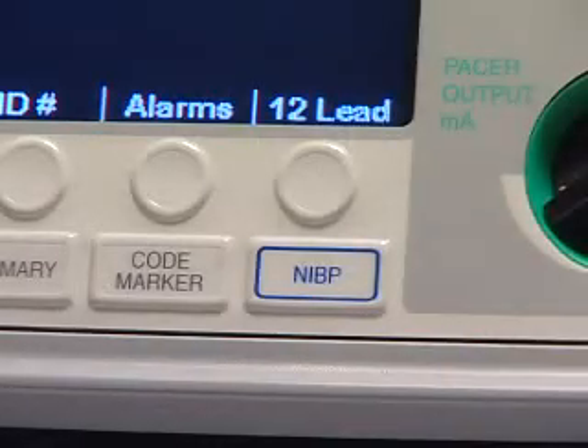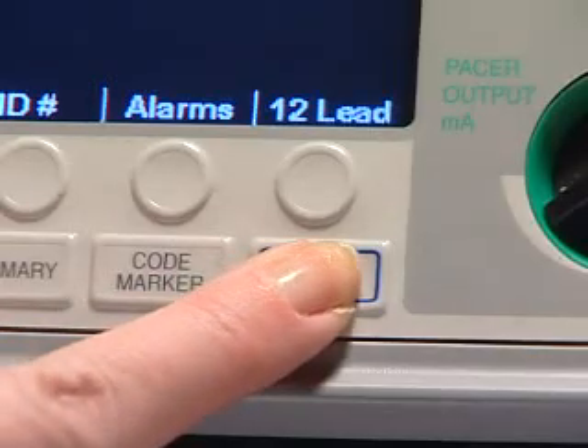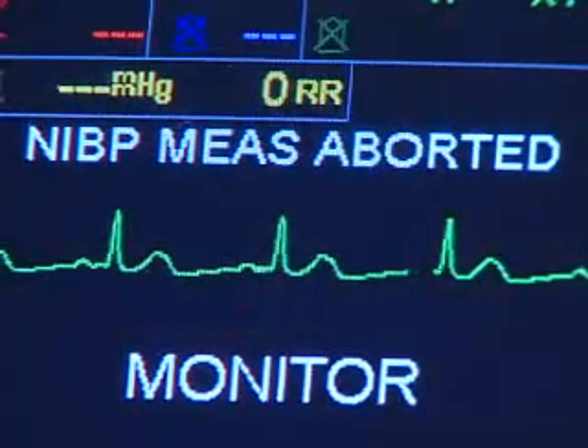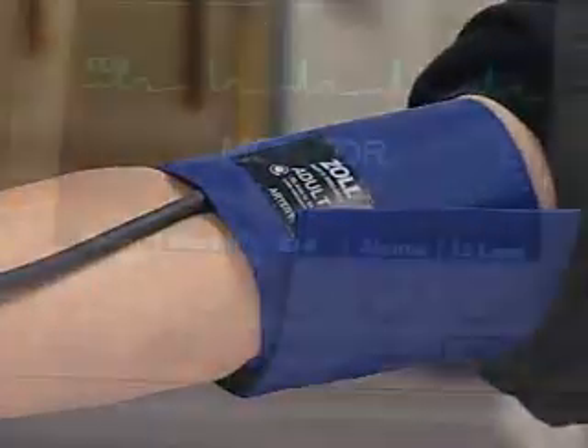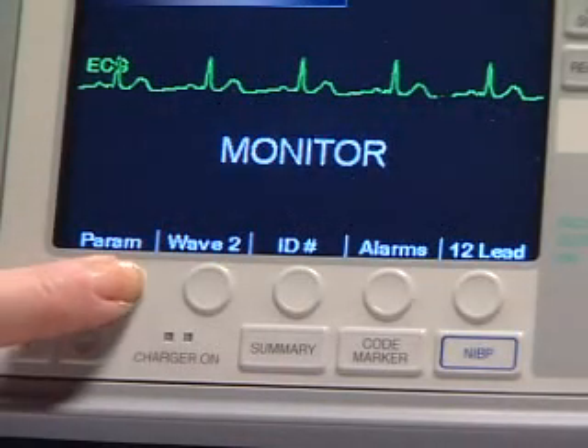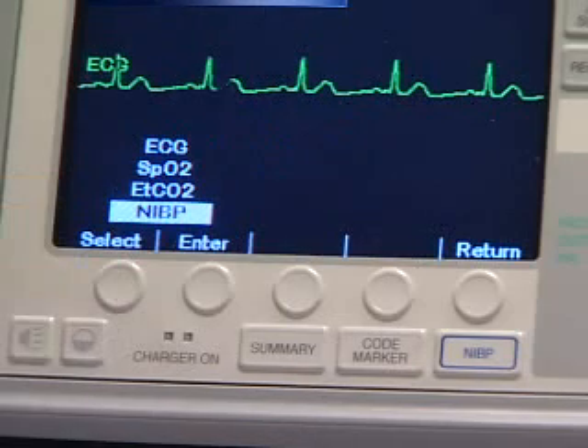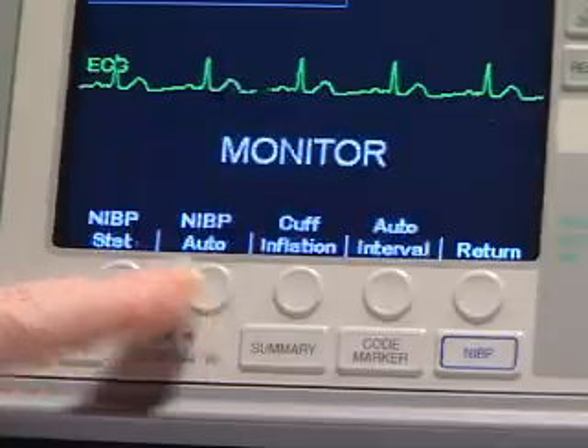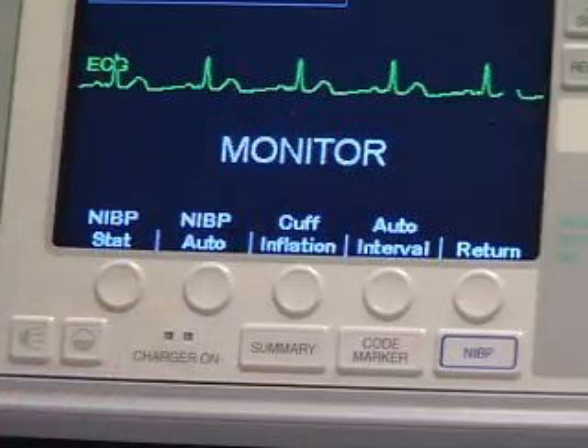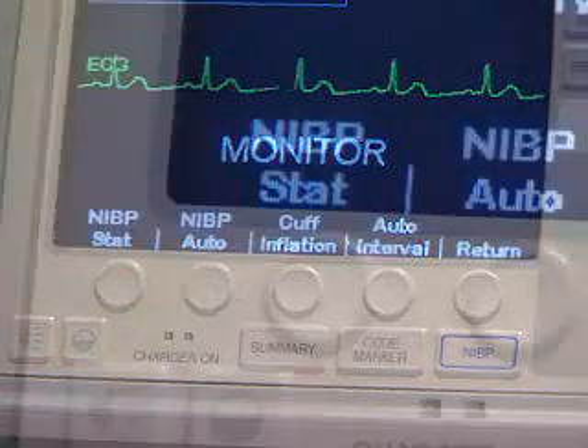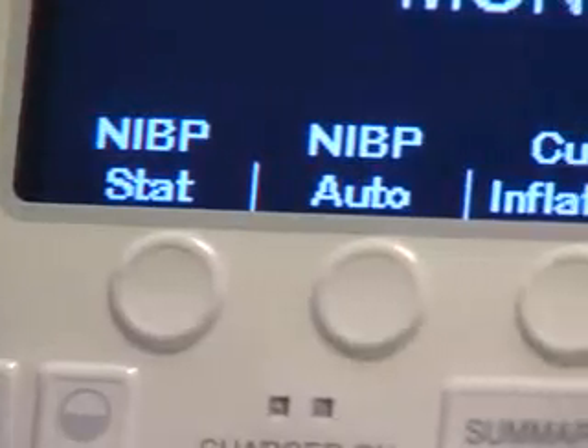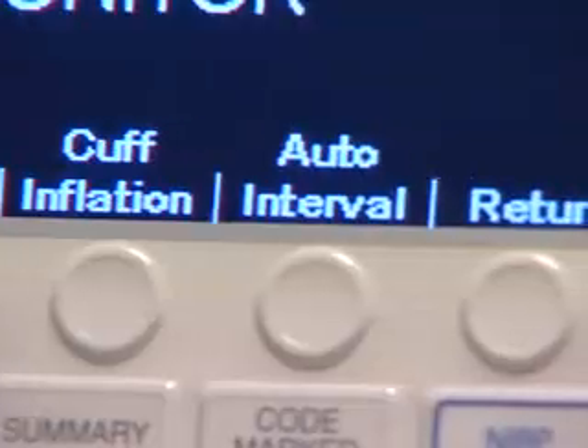The NIBP button on the front panel of the E-Series allows you to initiate and terminate BP measurements. Now apply the BP cuff to your patient. From the main monitoring menu, press the Parameter soft key to access the Physiological Monitoring Parameter menu. When NIBP is highlighted, press Enter. Press the soft key and the following will be displayed: NIBP Stat, NIBP Auto, Cuff Inflation, Auto Interval, and Return.